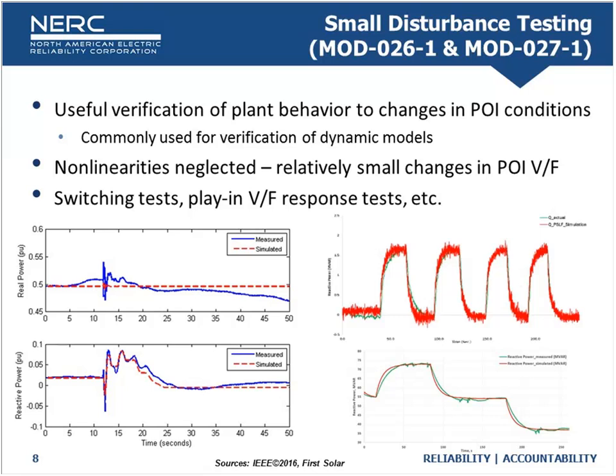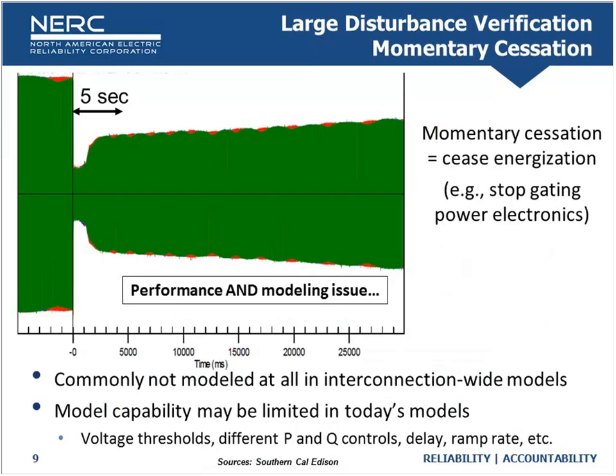However, when you get into the more severe large disturbance events, it's a challenge. For less than 5% changes in voltage reference or small changes in grid frequency, everything looks fine. But when you apply a fault, it's nearly impossible to test those effects — we don't go out and apply a fault onto the grid to do model verification. When faults do occur, it gives a great opportunity to see if the plant response at large-scale, large-disturbance conditions matches the model's performance.